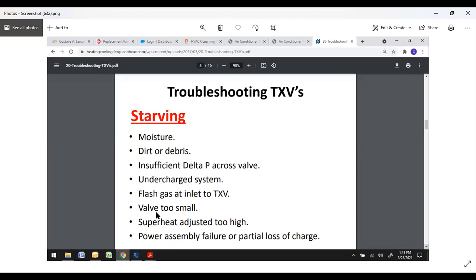If you have a valve that's too small, or a superheat that is adjusted too high, not enough charge is allowed to flow through. Power assembly failure or partial loss of charge. Sometimes you'll end up with a locked up TXV where that refrigerant coming out of the outdoor unit is hitting a brick wall because it's slammed shut, won't let anything through or very little. Other times it's just going to be partially shut, which is what we see usually.